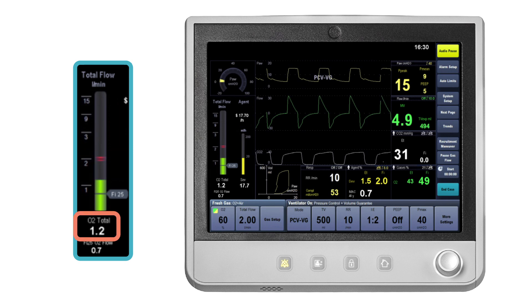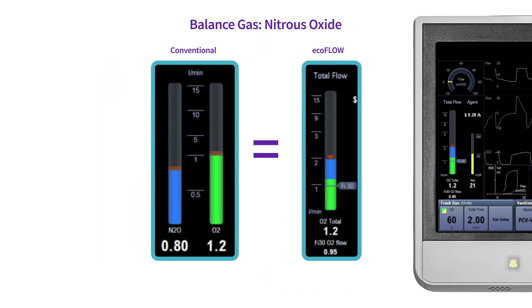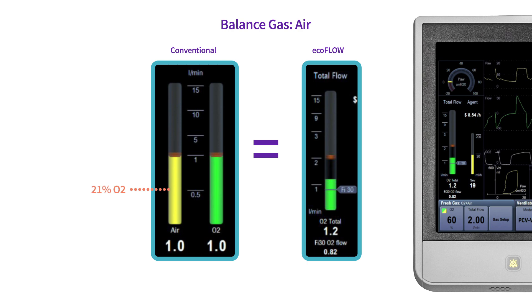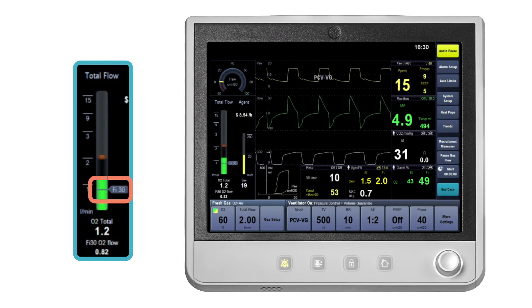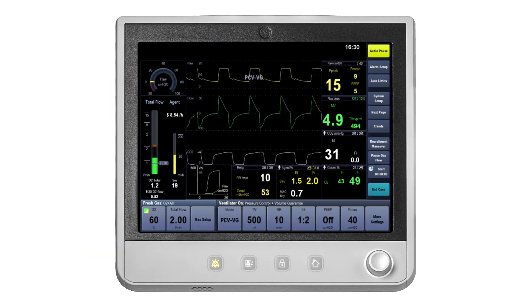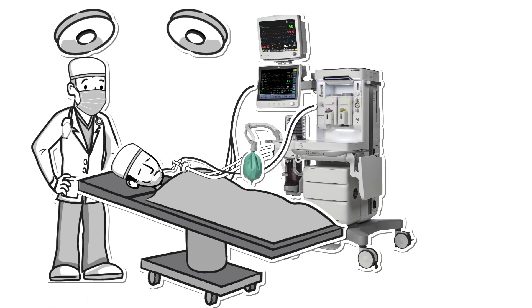Below the flow tube is the numerical display of the total oxygen content in the fresh gas flow. If nitrous oxide is the balanced gas, the numeric O2 total equals the set O2 flow. If air is the balanced gas, the numeric O2 total equals the set O2 flow plus 21% of the air flow rate. The FiO2 marker is a graphical representation on the flow tube showing the minimum O2 flow that is needed to maintain a preset inspired oxygen value. Below the numeric O2 total flow is the FiO2 total flow, which indicates the lowest oxygen flow needed within the total fresh gas flow to maintain a minimum FiO2 based upon the FiO2 flow marker value.